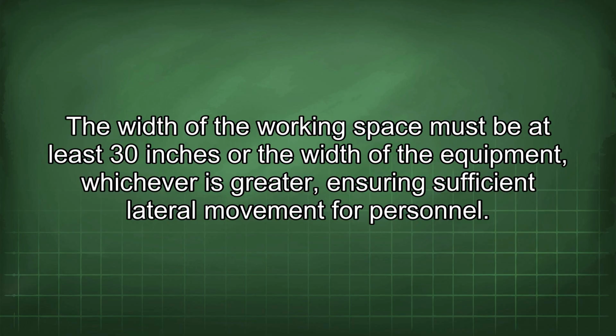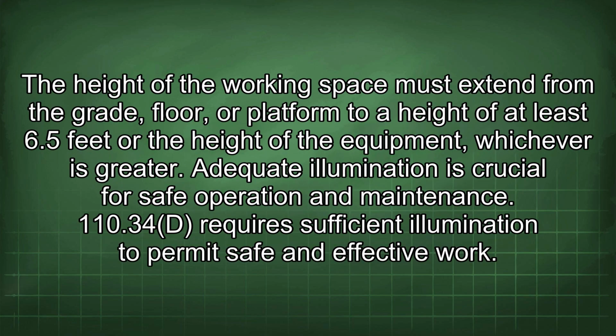The width of the working space must be at least 30 inches or the width of the equipment, whichever is greater, ensuring sufficient lateral movement for personnel. The height of the working space must extend from the grade, floor, or platform to a height of at least 6.5 feet or the height of the equipment, whichever is greater. Adequate illumination is crucial for safe operation and maintenance.